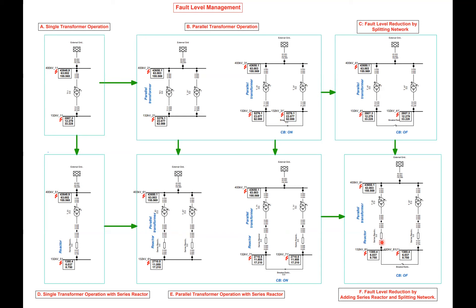So either by splitting the network or by adding a reactor in series, the fault current can be reduced. For example, comparing the 12 kiloamp benchmark: by splitting the network and adding a series reactor, the fault current is reduced substantially from 12 kiloamps to 6. Similarly, with parallel transformers it was 23, reduced to 12 by splitting, and then to 6 with a single reactor. Or using a single transformer, from 12 kiloamps to 6 kiloamps by adding a single reactor.